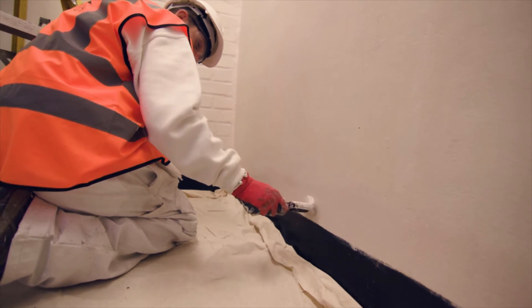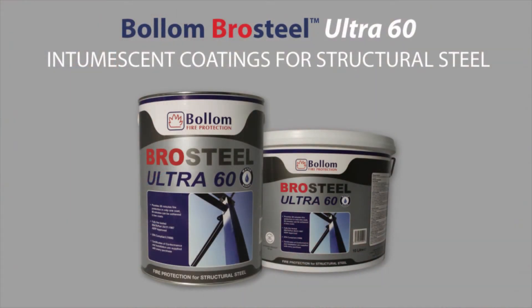At Bollom, we offer intumescent coating solutions for all vulnerable areas of buildings. Brosteel Ultra 60 is a thin film water-based intumescent coating that provides up to 60 minutes fire resistance to structural steelwork. In the majority of cases, 30 minutes fire protection can be achieved with one coat and 60 minutes with two coats.